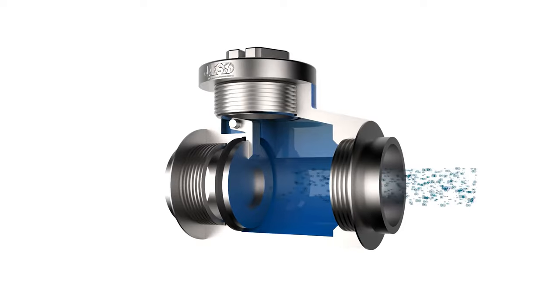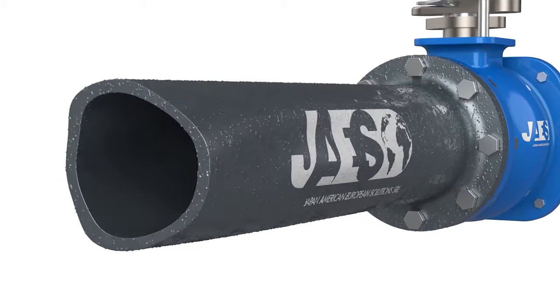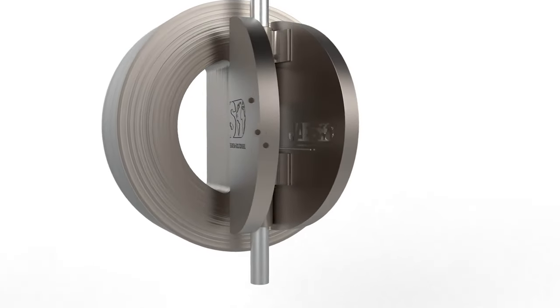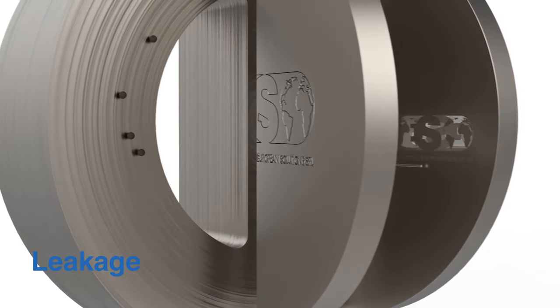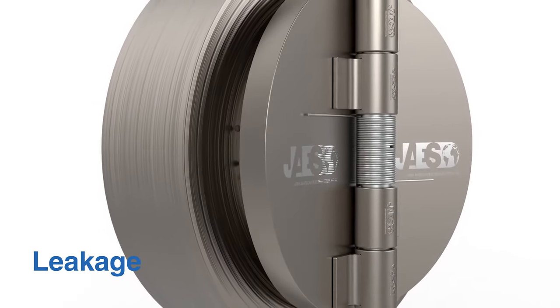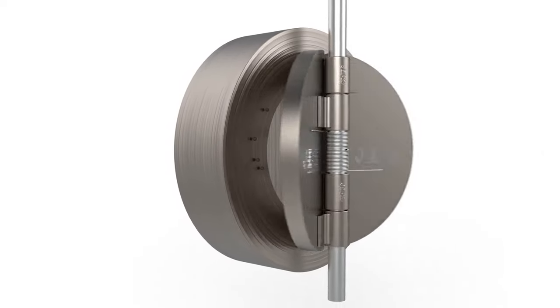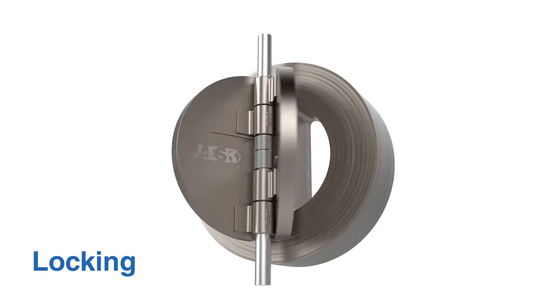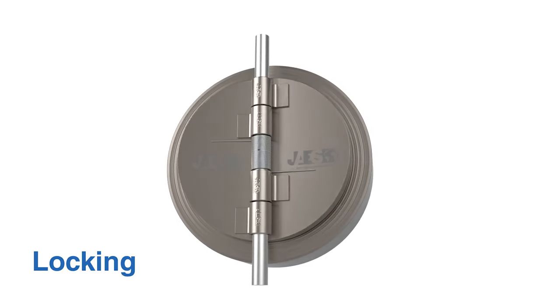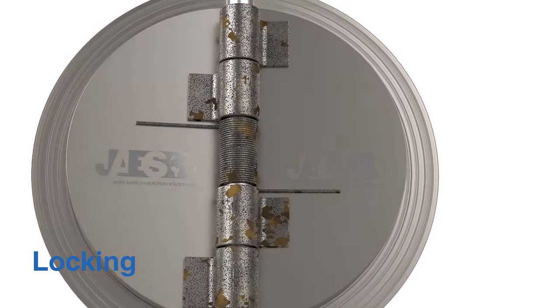The main advantage of the check valve is the absence of backflow and water hammer, which could damage the pipes. However, this valve also has some disadvantages, such as leakage — when a large amount of grime is placed between the base of the valve and its disc so that the valve doesn't close properly. Another disadvantage is locking, which occurs when poor sliding of the guide doesn't let the disc close completely, and most of the time the cause is due to oxidation of the components.